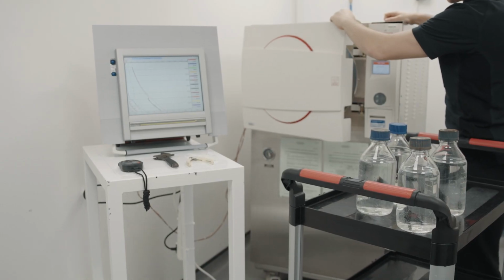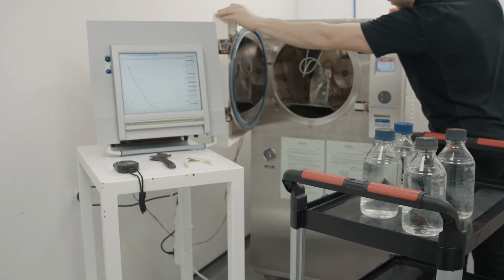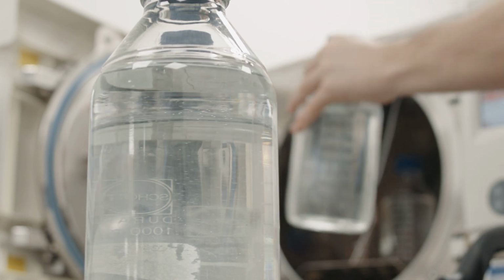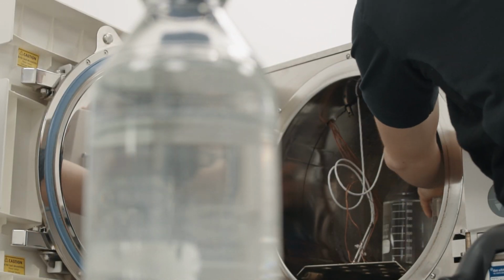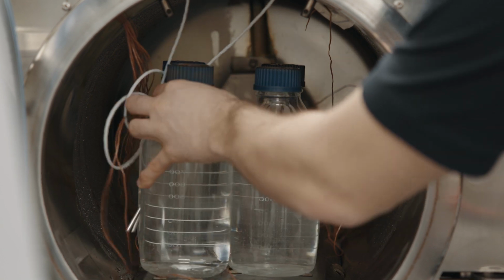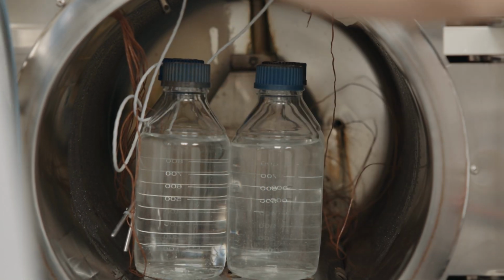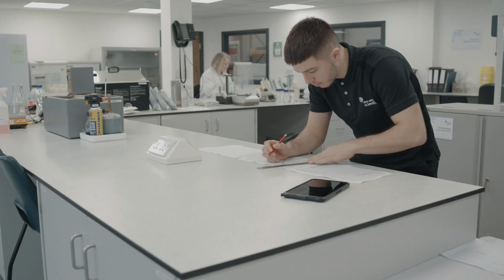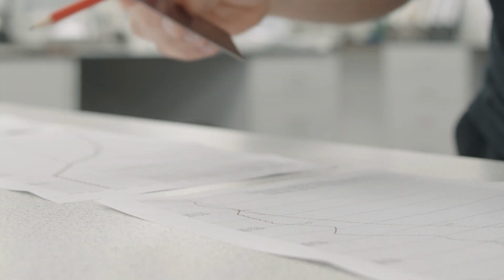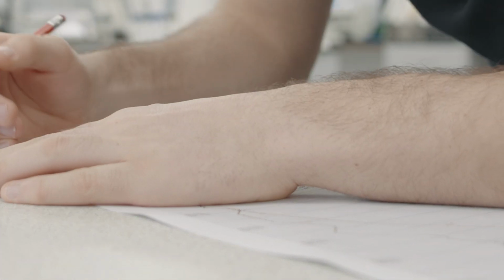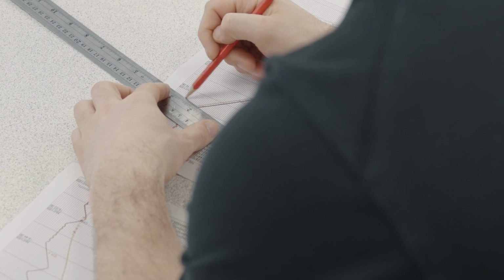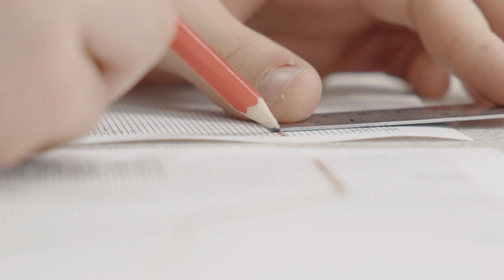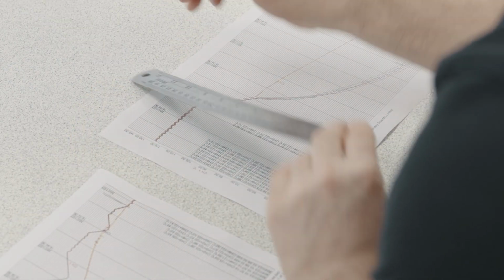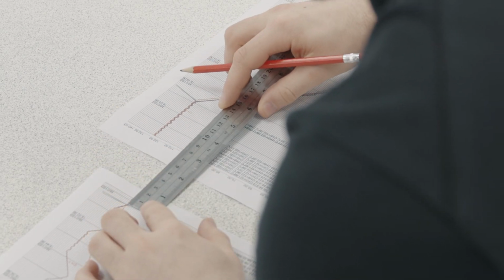An autoclave that has been calibrated and whose instruments have been proven to read accurately only means the autoclave is performing correctly. It does not prove sterility. For that, you need to look to validation. The process of validation allows us to confirm by measurement that an entire load has achieved the required temperature for the required time period. A validation, by its very nature, encompasses a calibration as part of the process.